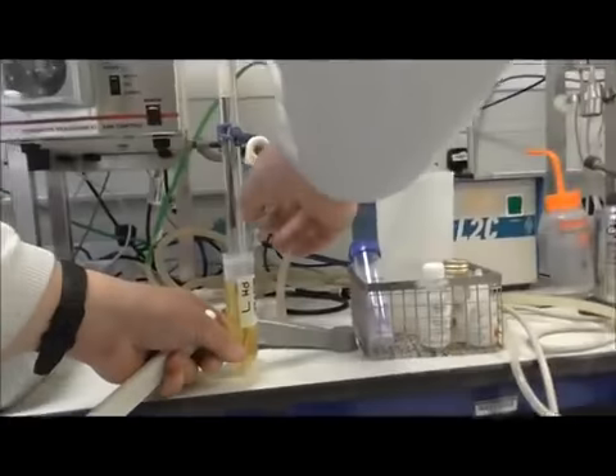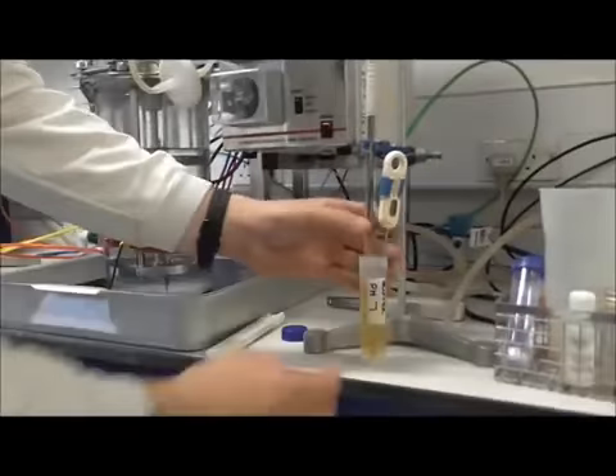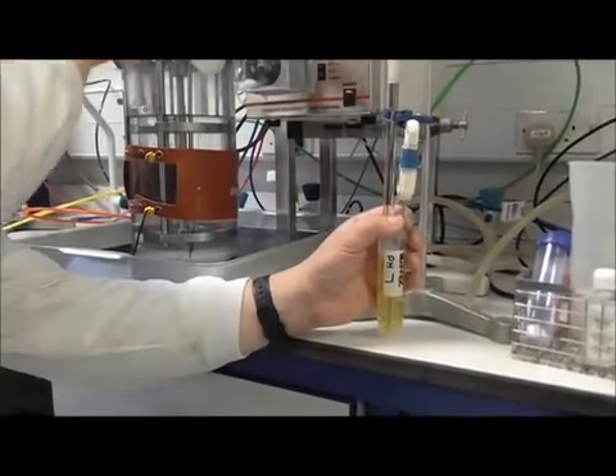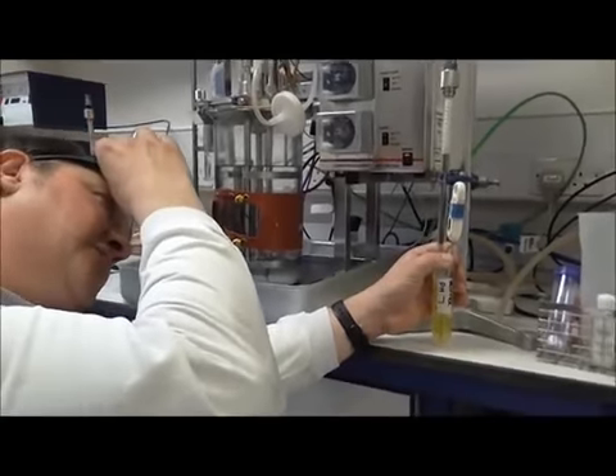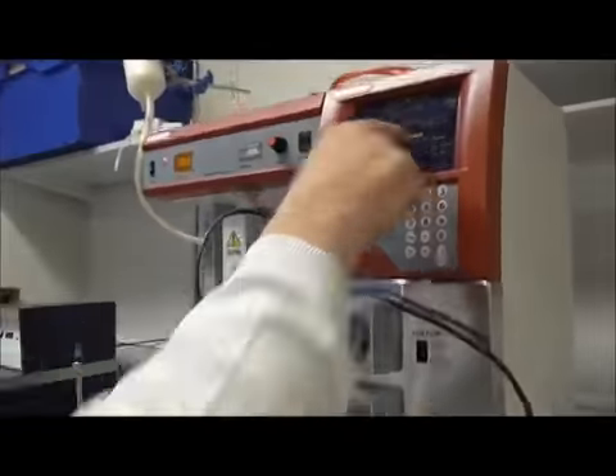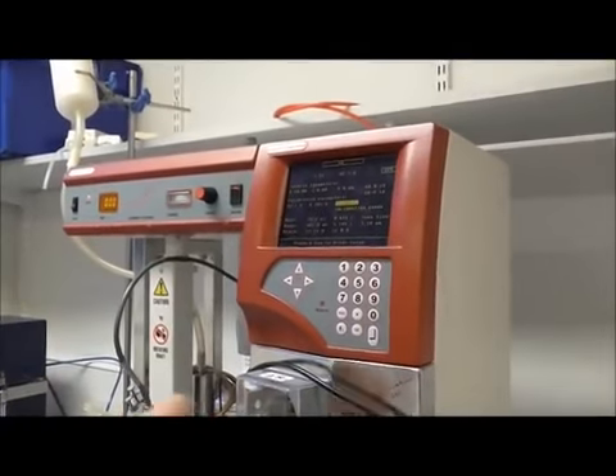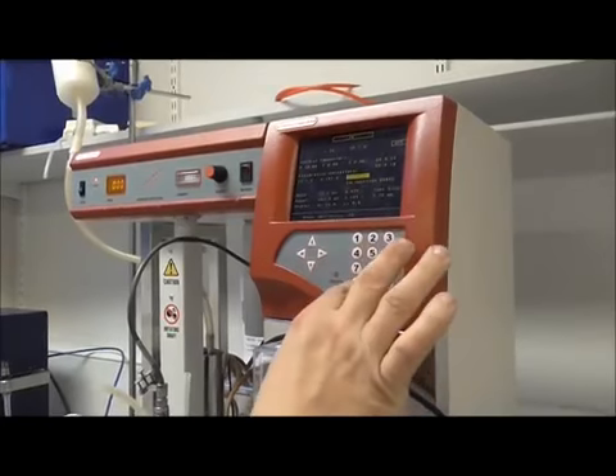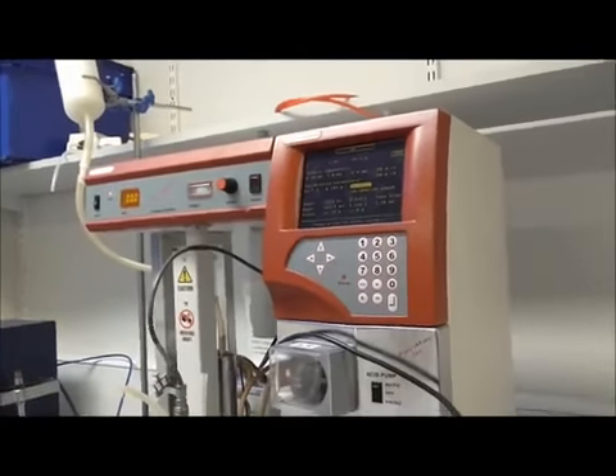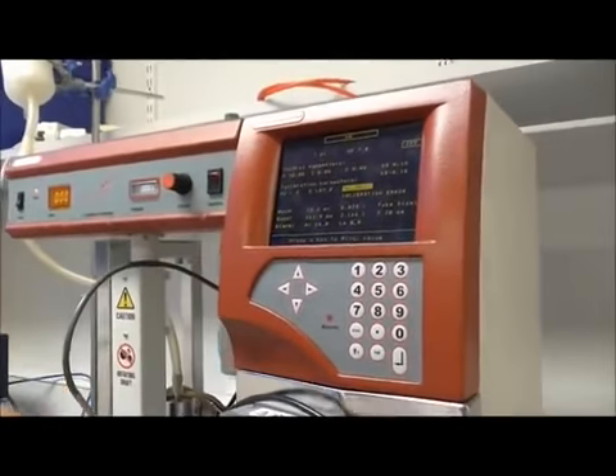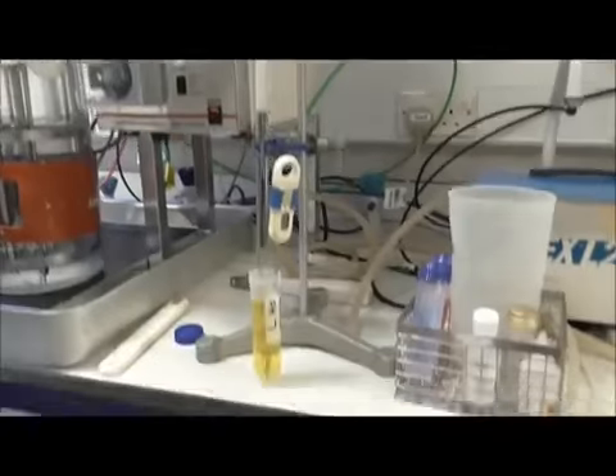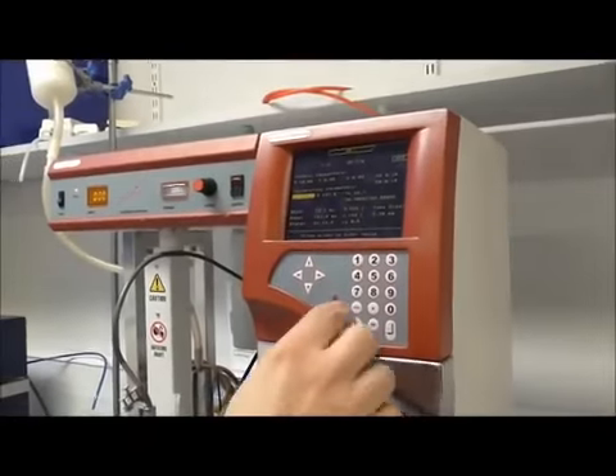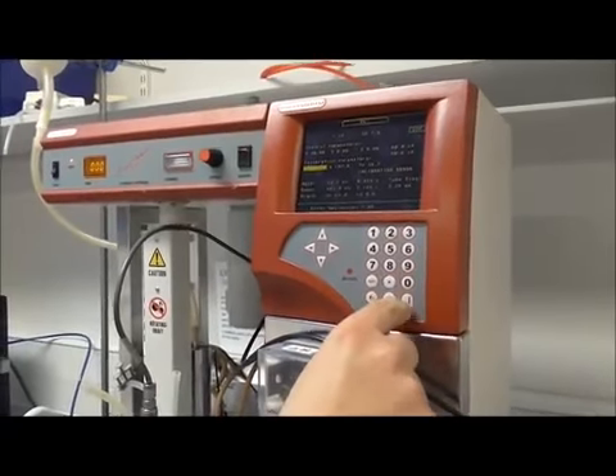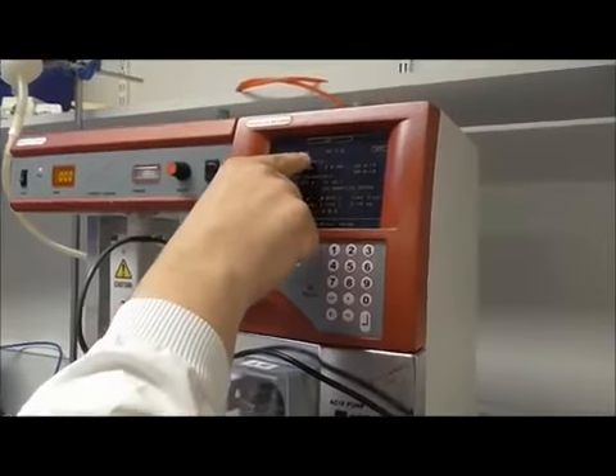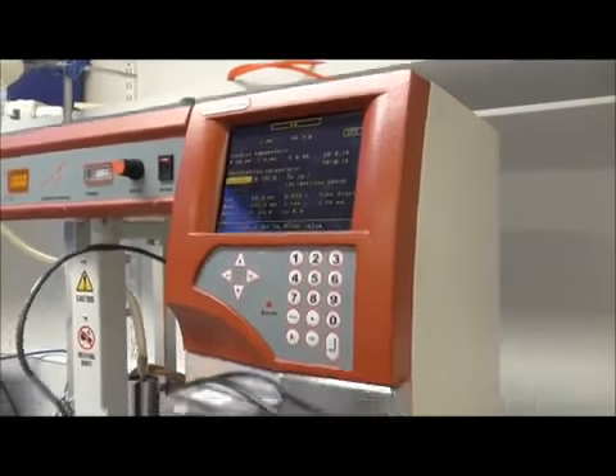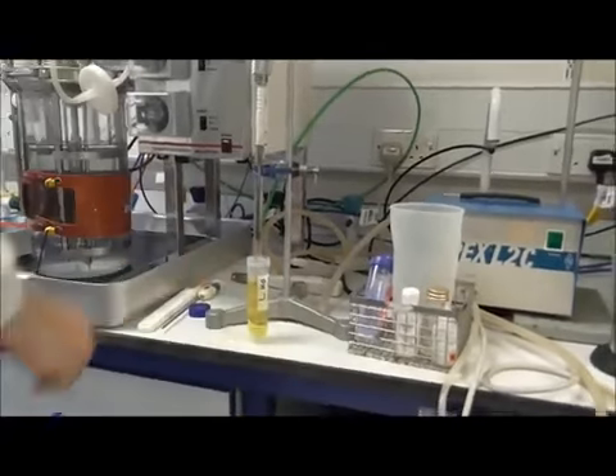So move the cursor block down to temperature, and with the aid of a nice little digital thermometer we put that into the buffer. I make that 20.7 degrees. So, well, look at that, 20.7, coincidence. So 20.7, enter. So we let the reading settle. So we need to confirm that is buffer 7. So we scroll across to 0 and we go 7.00, enter. And there we are, pH 7. So we can remove the temperature probe.